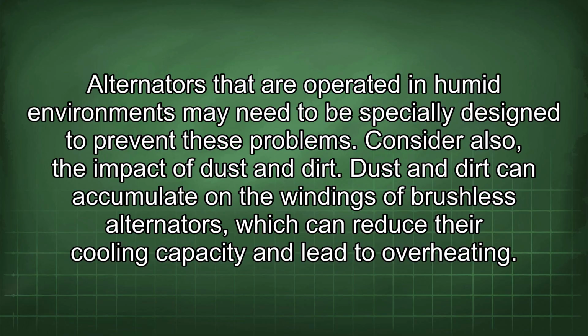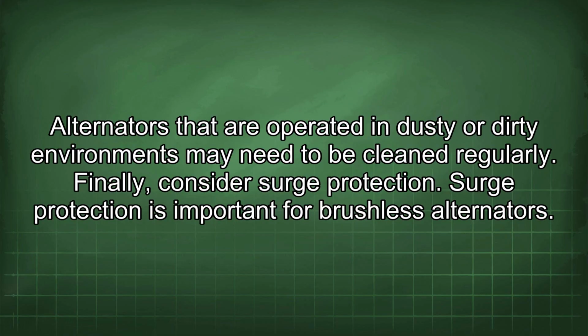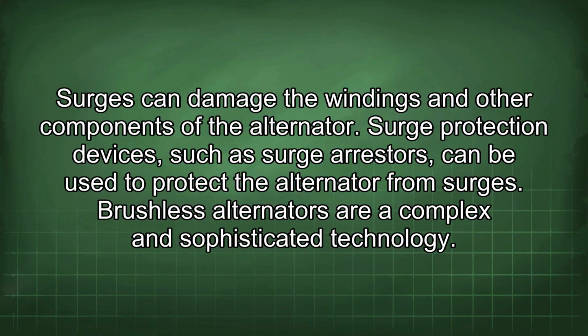Consider also the impact of dust and dirt. Dust and dirt can accumulate on the windings of brushless alternators, which can reduce their cooling capacity and lead to overheating. Alternators that are operated in dusty or dirty environments may need to be cleaned regularly. Finally, consider surge protection. Surge protection is important for brushless alternators. Surges can damage the windings and other components of the alternator. Surge protection devices, such as surge arresters, can be used to protect the alternator from surges.